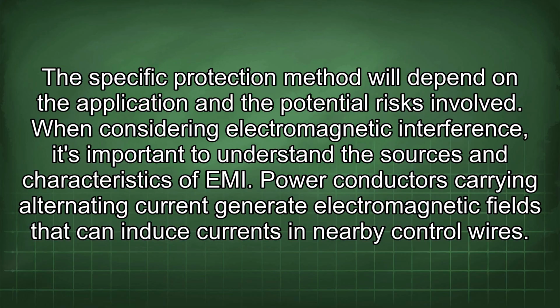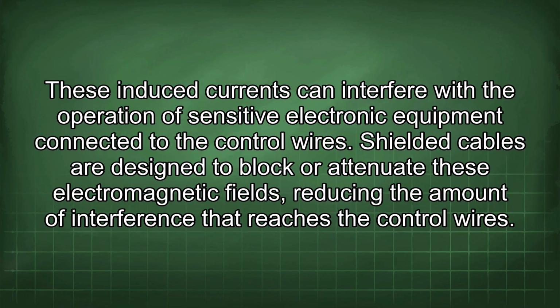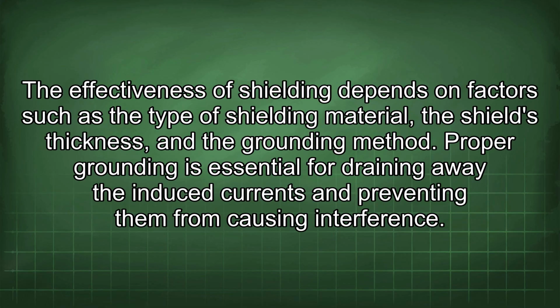When considering electromagnetic interference, it's important to understand the sources and characteristics of EMI. Power conductors carrying alternating current generate electromagnetic fields that can induce currents in nearby control wires. These induced currents can interfere with the operation of sensitive electronic equipment connected to the control wires. Shielded cables are designed to block or attenuate these electromagnetic fields, reducing the amount of interference that reaches the control wires. The effectiveness of shielding depends on factors such as the type of shielding material, the shield's thickness, and the grounding method. Proper grounding is essential for draining away the induced currents and preventing them from causing interference.